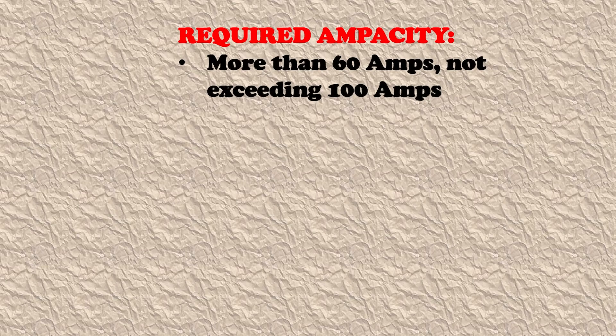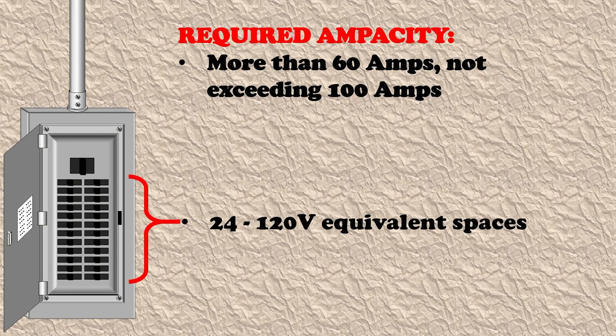The next situation is where we have more than 60 amps but not exceeding 100 amps, inclusive of that 100 amps. So if our calculated required ampacity falls above 60 and not exceeding 100 amps, we are required to have 24 of these 120-volt single pole equivalent spaces in this panel. Again, it's not important whether there is a central electric furnace provided for or not — the code does not stipulate that in this range.